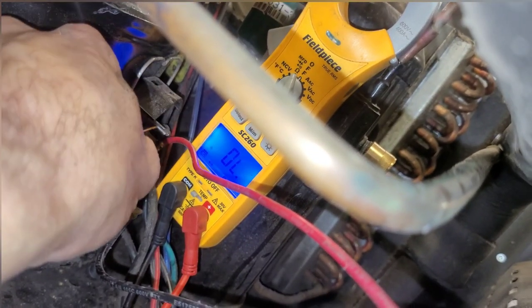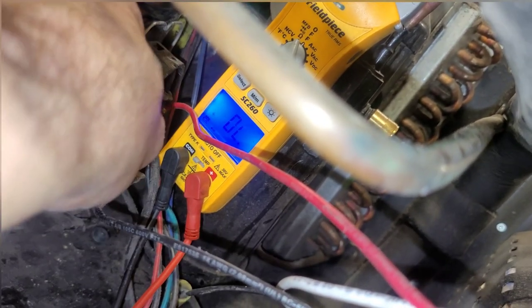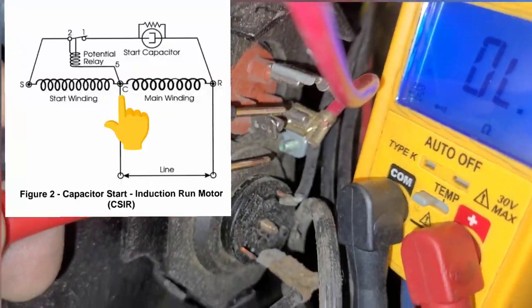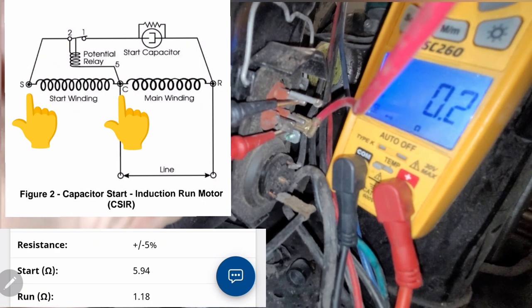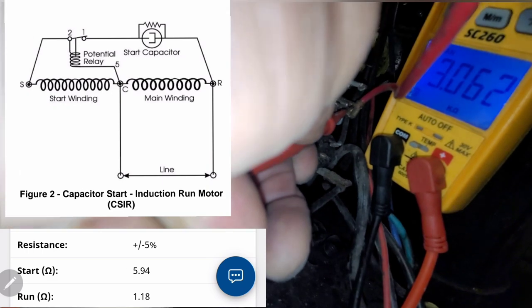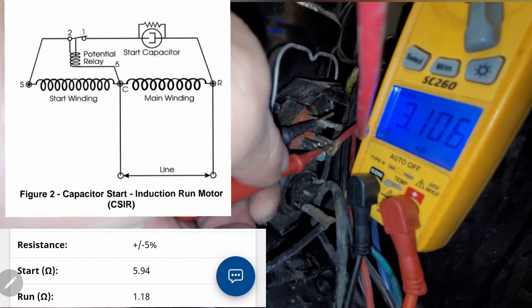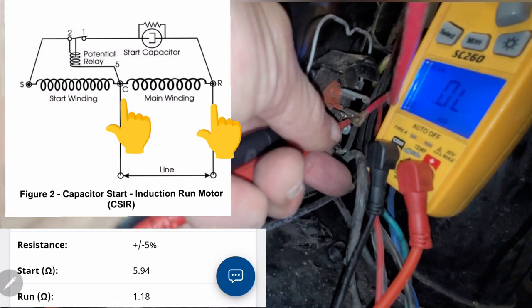It was hard to get down in there and reach, but I was able to get it on camera. I get an open between common and start — open. And then across my other terminals I get 3.11 kΩ — between start and run, and run and common, 3.1 kΩ.